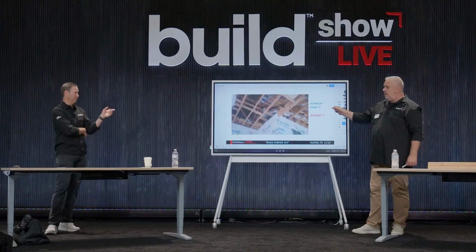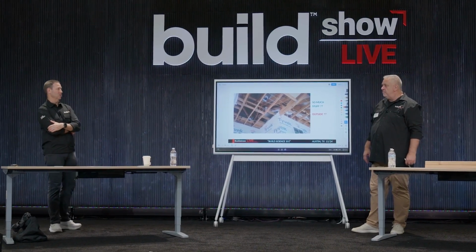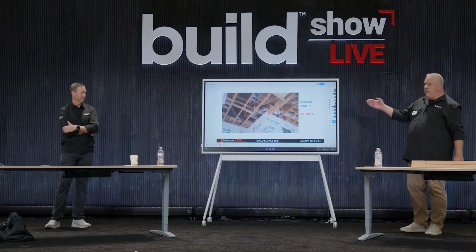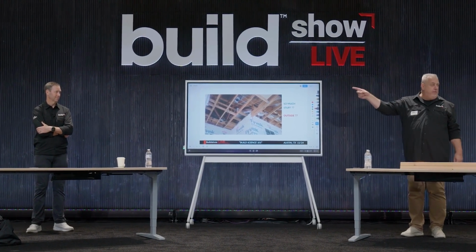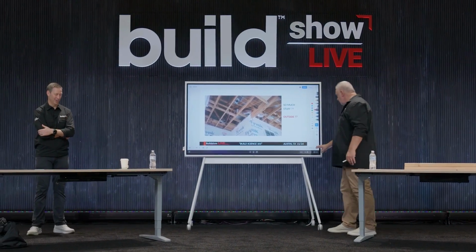We could drive 5 miles from this location we are today and see 50 houses under construction that have that same exact detail with ducts out of the conditioned space. And I'll leave you with, I couldn't help myself, and I got far enough away from Peter's kicking range, and I told the builder he would have been better off if he put the unit outside the house, ran it up and across the roof. It would have performed better, because it was a hell of a lot cooler than inside the attic. That's for sure.